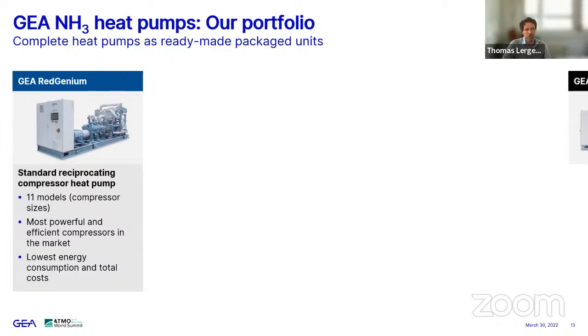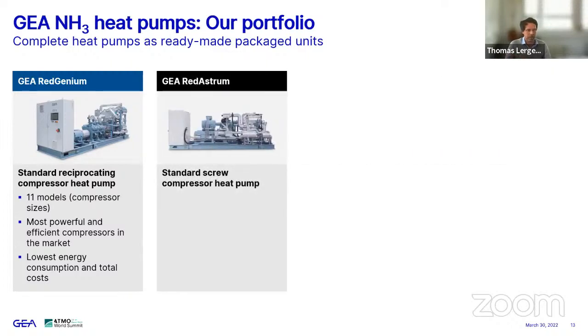There's a screw compressor counterpart. So basically its sibling, its sister or its brother of this RedGenium is called RedAstrum. This is the same idea, the same design, but based on a screw compressor heat pump. There are 7 sizes in total for this standard screw heat pump. It is very compact, very low vibrating, and requires very little maintenance with our high-end screw compressors that, like the piston compressors, are also coming from our own development and production for many, many decades.